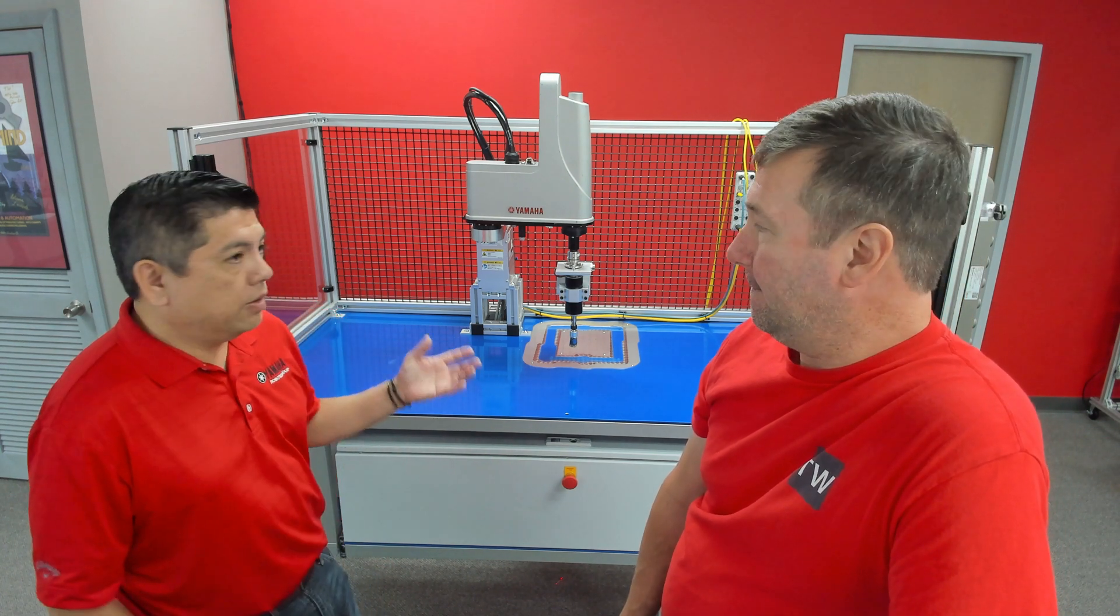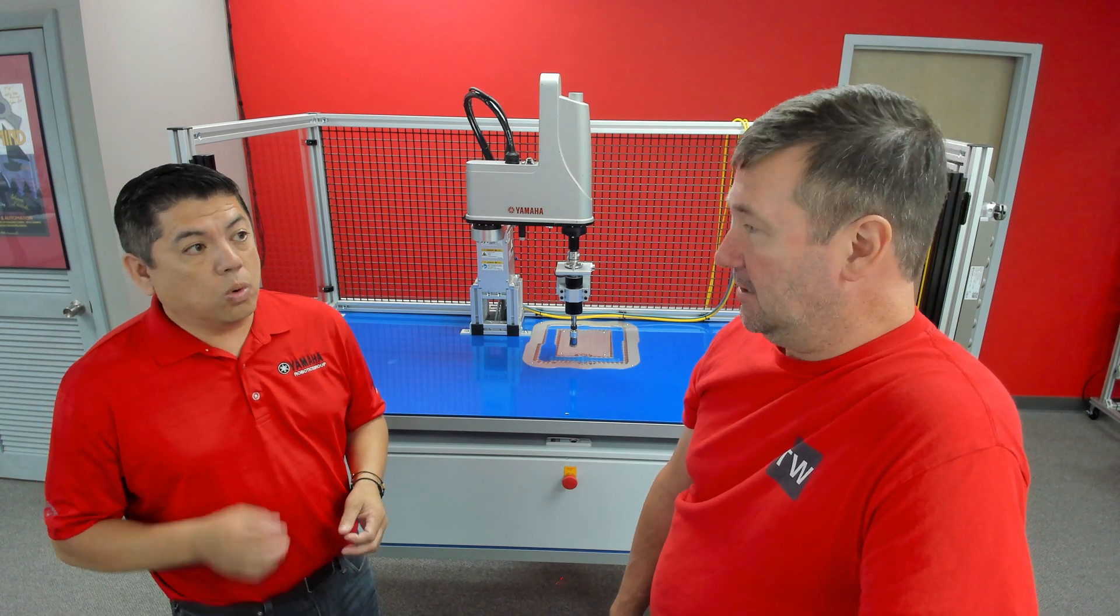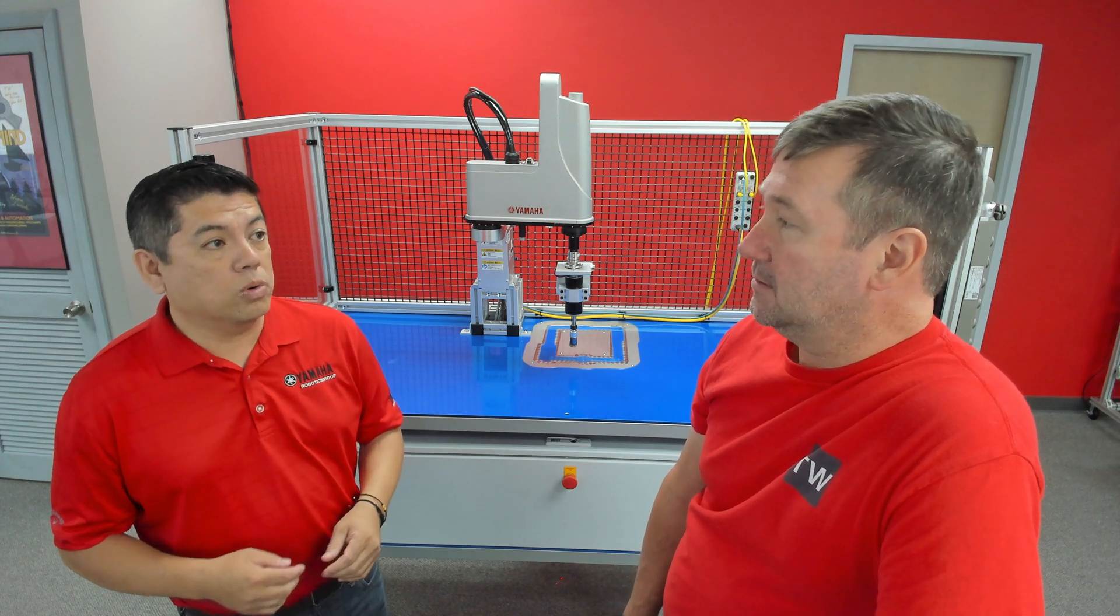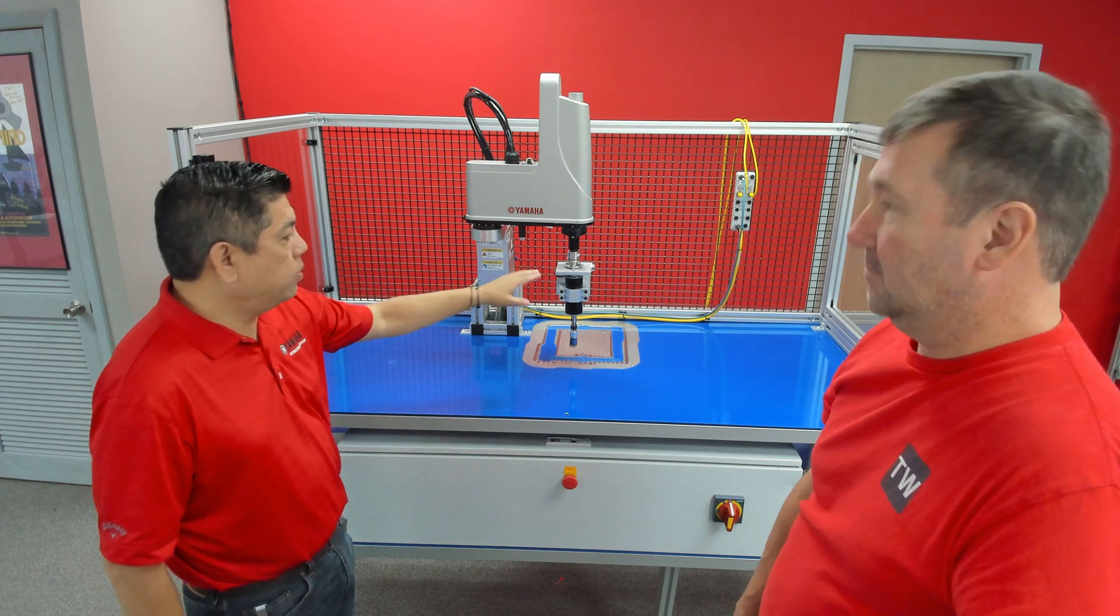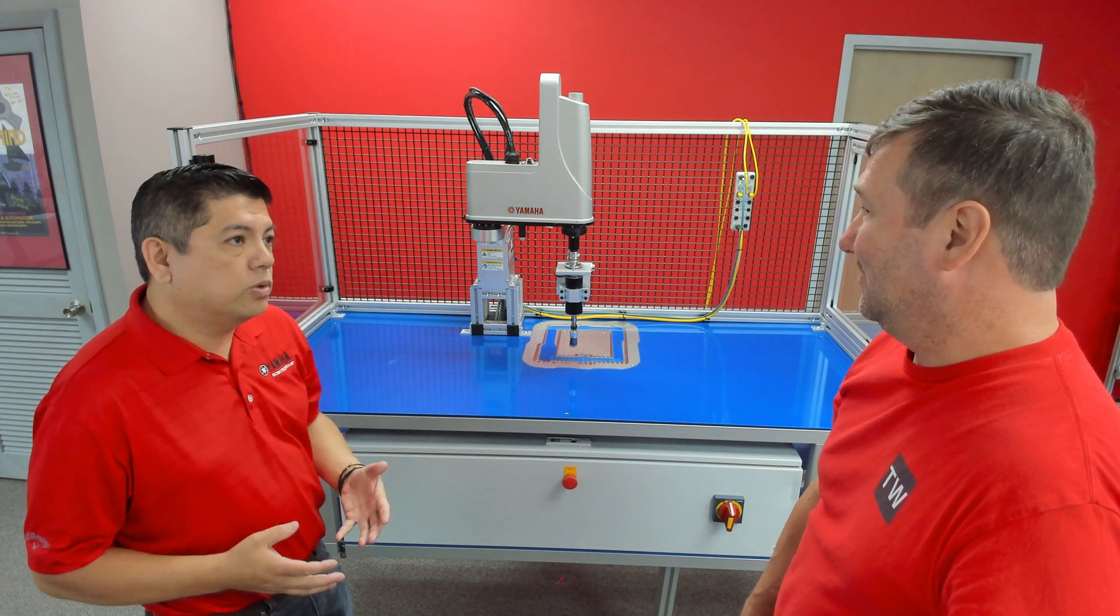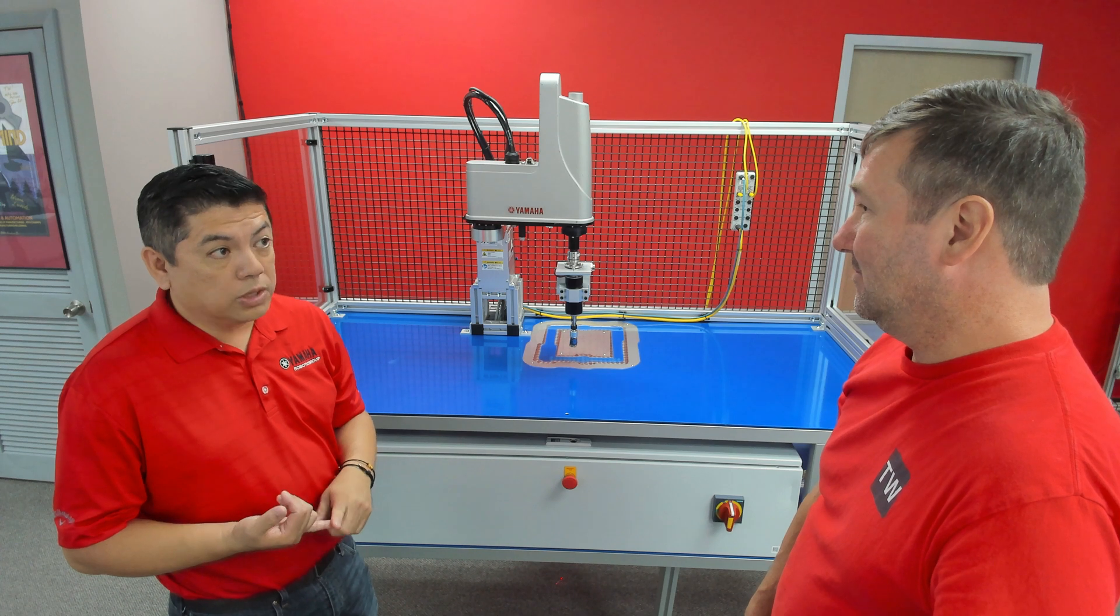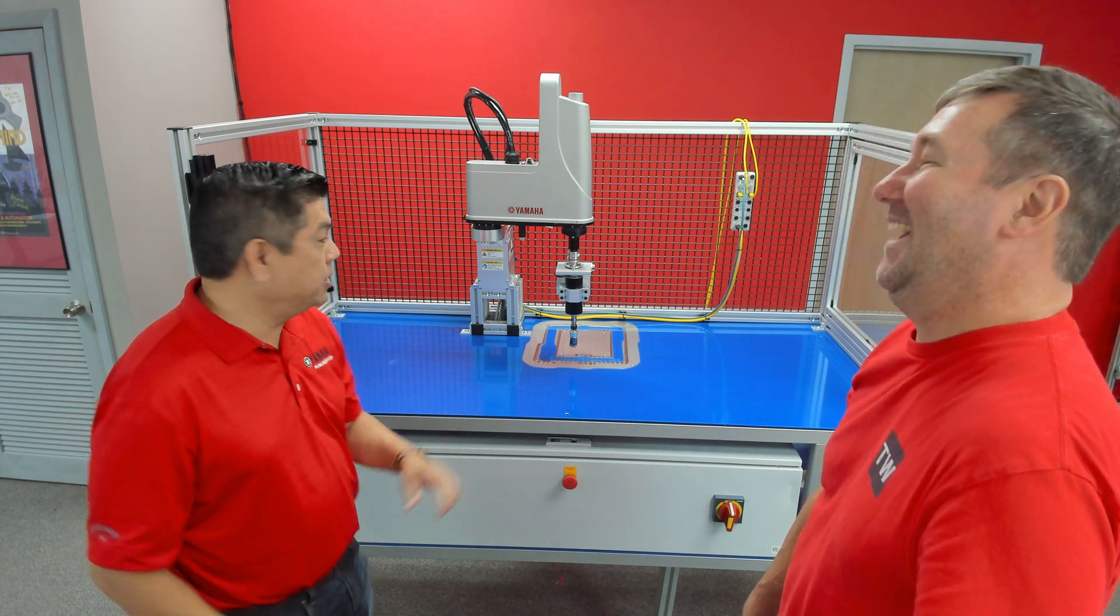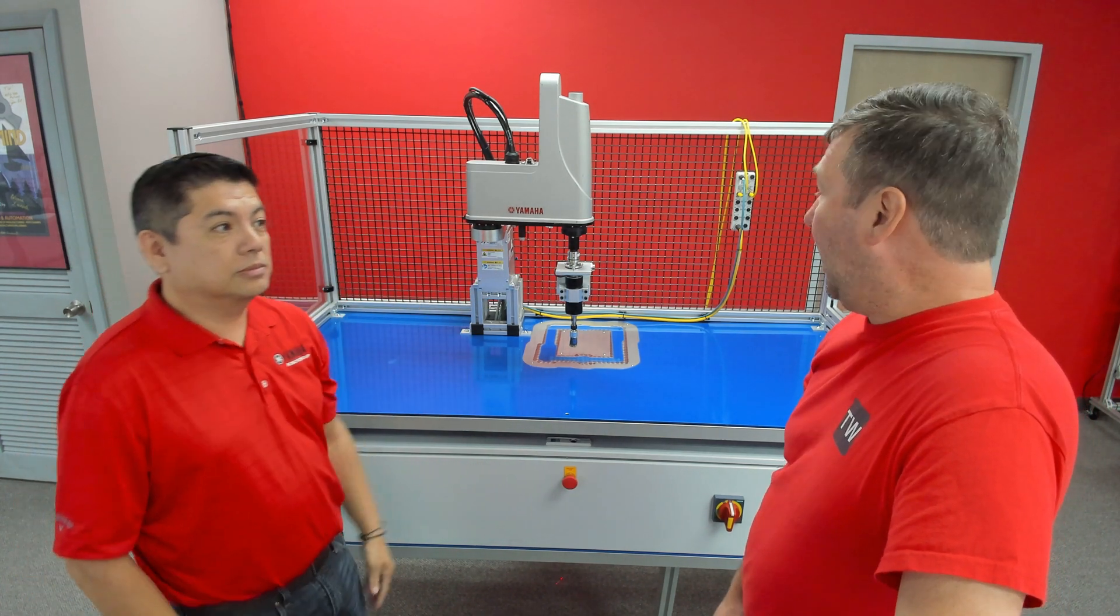So this SCARA is a four axis robot. That means it has four servo motors on it. So origining A1, A2, A3, A4, those are the four axes that we need to origin. And on this robot, it has three sensors that it origins to, and one axis is a torque origin. That's the actual Z axis. So in Yamaha's world, we have three choices of how we origin a robot. We can either origin to torque, we can origin sensor, or we can just origin in what I call la-la land, which means make a jig for it and origin it anywhere you want and call that zero.